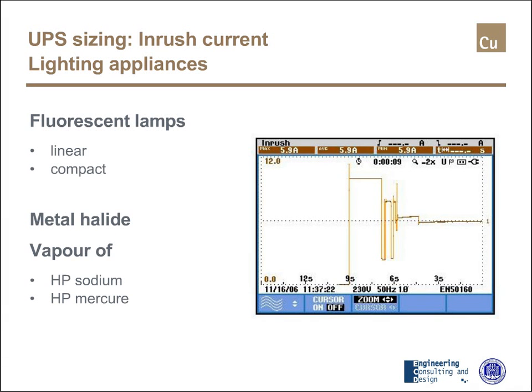In the picture, we see the envelope of the RMS value of the inrush current for a series of lamps. You can see multiple lines. It is evident that in the first segment the current is much larger than in steady state — on the right of the graph the current appears nearly zero, but it's not zero; it is simply the steady-state current.